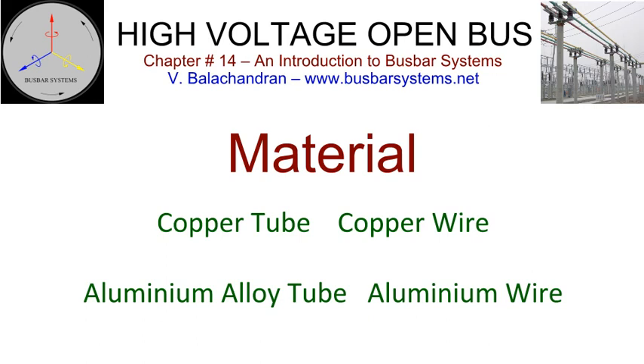All the accessories such as clamps, connectors, bends, laminates, end caps, corona rings are all made of aluminium castings or fabricated from aluminium alloy sheets and extrusions. The conductivity of aluminium alloys is expressed as %IACS, International Annealed Copper Standard. Aluminium sheets 1350, 65%. Aluminium tubes 6101, 55%.